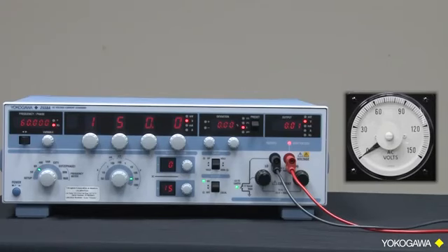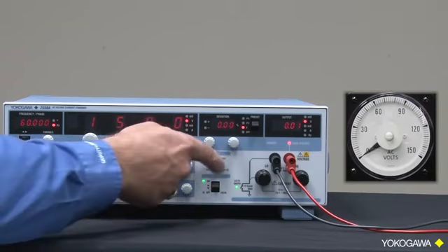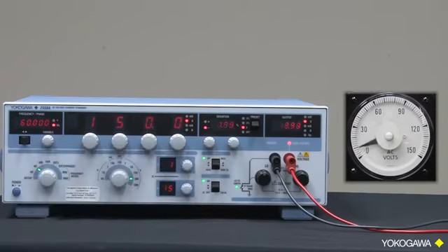With the meter sitting at 0 volts, I simply press the sweep button and the 2558A will sweep the voltage to the panel meter in a very controlled manner. The sweep function will also overscale the output to the meter by 20%, causing the meter movement to hit the pointer stop. This is done to see if the meter would stick if an overvoltage condition occurred.